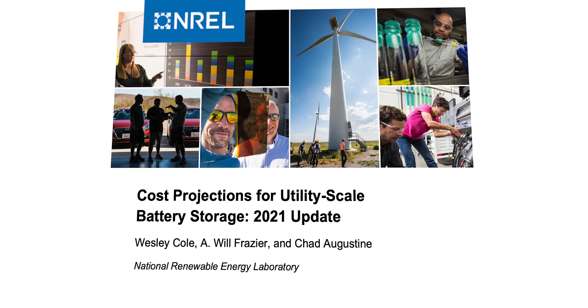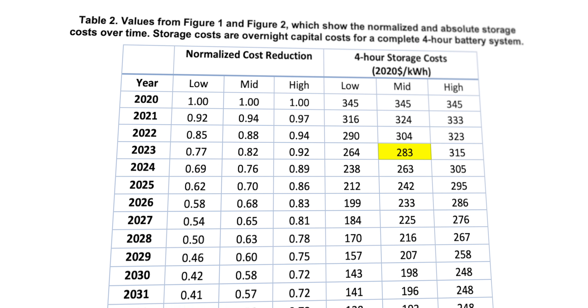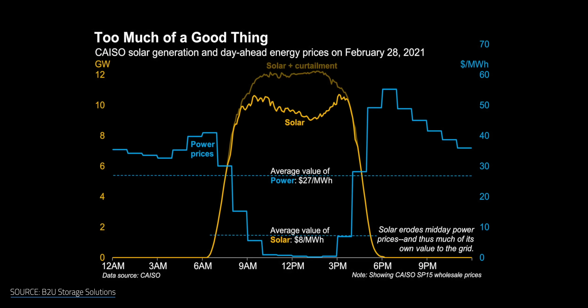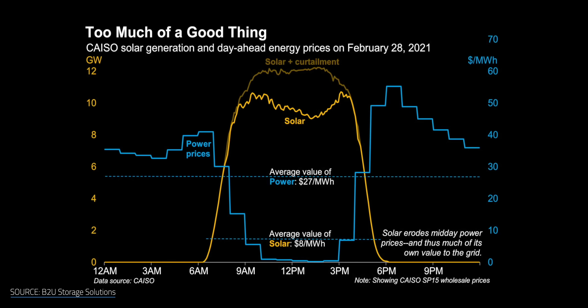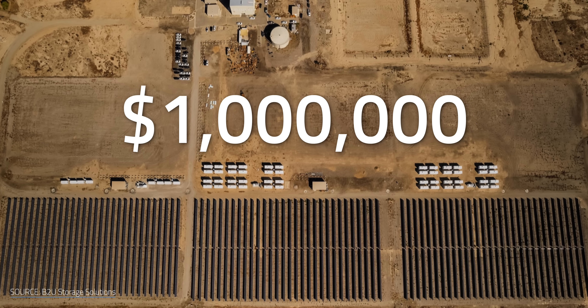For context, a National Renewable Energy Lab study put the cost for a similar facility in 2023 at around $283 per kilowatt hour, and they didn't project costs to dip below that $200 per kilowatt hour until 2030. And speaking of money, the EPS controller doesn't just monitor the batteries — it monitors the market for the best deals too. By taking advantage of both predictable daily price shifts and unexpected price hikes, it automates bids and sends them directly to the California grid. Tesla has similar functionality with their Megapack installations. Essentially, it collects energy when the sun is shining and that power is cheap, and then when people get home at night, it sells the energy to the grid when it's most desired and valuable. It's a sort of buy low, sell high arbitrage strategy that has generated over $1 million in revenue for B2U in 2022.